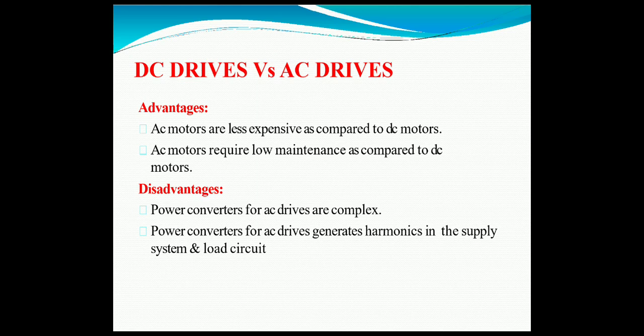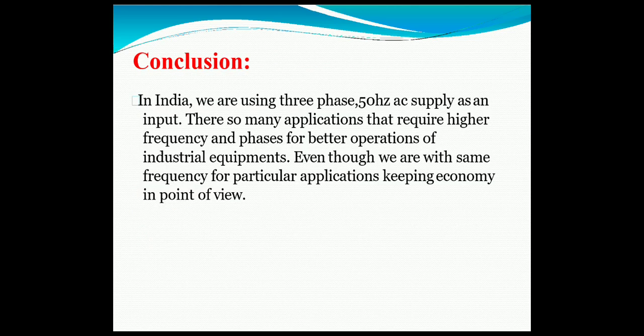Comparing AC and DC drives on the basis of advantages and disadvantages: AC motor drives are less expensive compared to DC motors, and AC motors require low maintenance compared to DC motors. However, power converters for AC drives have very complex circuitry, and a power converter for AC drives generates harmonics in the supply system and also in the load circuit.